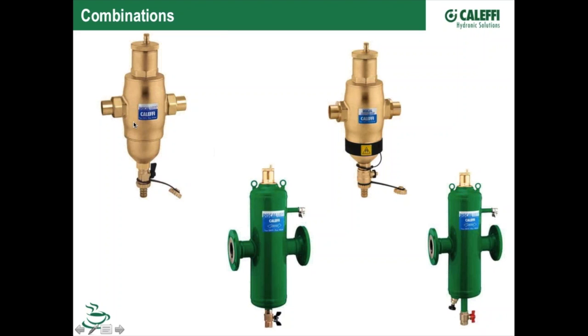One question that comes up when we present this to somebody or they consider using it, they say, well, where should I put it in my piping system? You told me that I want to get my air at the hottest point in the system, which is right at the coming out of the boiler, on the supply coming out of the boiler. That's true. And we want to catch the dirt before it gets into our boiler, into our pump, into our system. This would really be well used at the return. So yeah, it is a bit of a toss-up there. I don't have an exact answer for that.